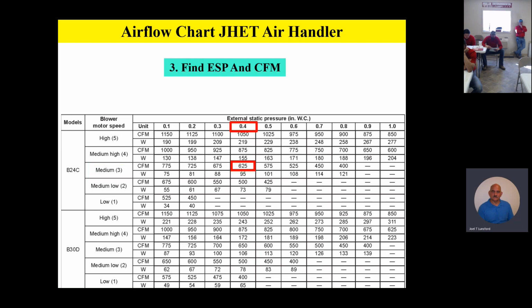You then measure your external static pressure. Let's say in this example, it was 0.4 inches of static total. You then correlate, or swing over from your model, your speed tap, and then your static pressure. In this example, that B24C on medium speed tap at 0.4 inches of static is blowing 625 CFM through the cabinet. You'll also notice right below that it says 95. That's the wattage that motor is pulling at that airflow measurement.